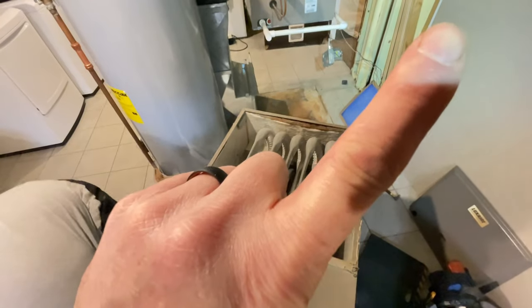All right, we have updates. I got this furnace dislodged, and you can see there's a crack, split there, split there, pretty much a split in all the cells. Yeah, it's just a hairline split right there. Pretty much one in every single one. So yeah, I'll leave the description right here.